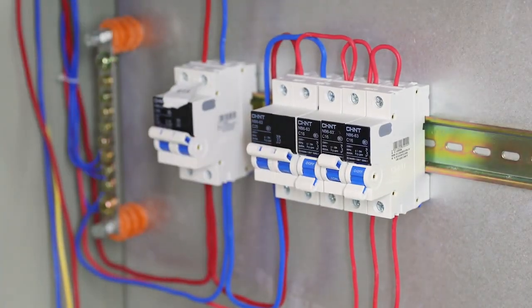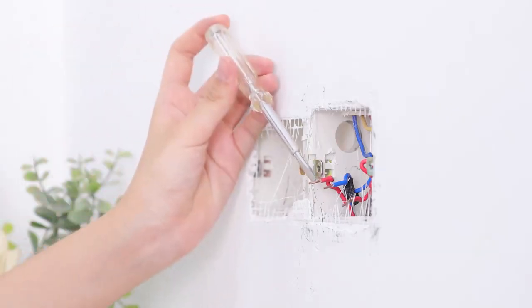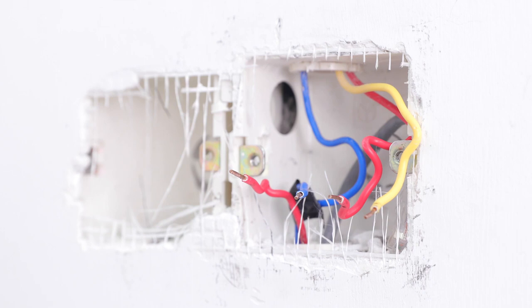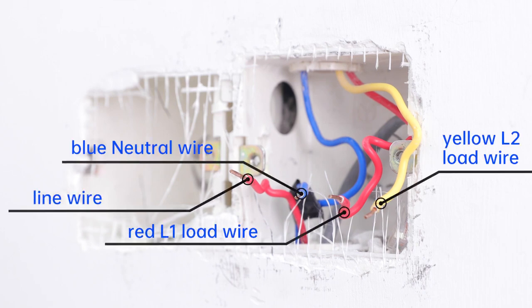The first thing you must do is to turn off the circuit breaker, and remember to use the voltage detector to double check the power is off before you start wiring and installation. Now you can identify the wires. We have blue neutral wire here, line wire may be red and carries power into HyPanel, and here are yellow L2 load wire and red L1 load wire. They carry power out to your lights. Note that your wire colors may be different from ours here.